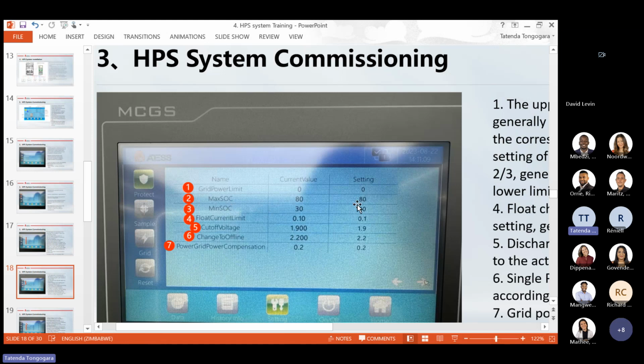And then max SOC, minimum SOC. This is for battery start stop, your generator start stop. So minimum is start, maximum is stop. You can set them depending on what you want or what your client wants. And then we have cutoff voltage. When it comes to battery settings, I prefer you get the information from the battery manufacturer. But if you are not sure, you can send us the nameplate of the battery. We can calculate these values for you. For cutoff voltage, for most lithium batteries, the cutoff voltage is 3 volts.